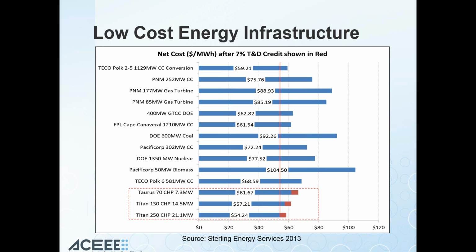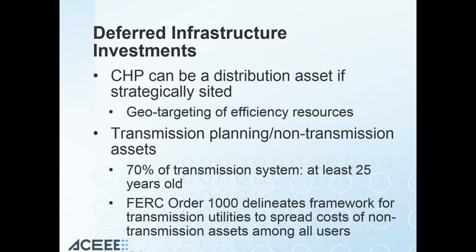Here's another chart showing the all-in cost per kilowatt-hour, or megawatt-hour in this case, for different technologies. At the bottom you can see three different options for CHP compared against more conventional technologies like gas turbines, baseload coal, and combined cycle. If you look at the cost of a simple combustion turbine versus a cogen unit with a heat recovery unit, certainly the cogen is going to be more expensive on the front end. But compared to a combined cycle, where efficiencies start to approximate each other, the difference isn't so much.